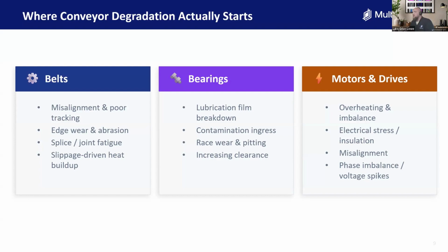And I think that there's something that's forgotten when we look at condition monitoring. It's for the operational zone - no, it's not. It's a lot of baseline data that can be used during that installation of quality, that commissioning, that understanding. And it was one thing that always used to blow my mind. You get a factory acceptance test, and there was not one standard in there about normal operating conditions. Not many OEMs even classified the vibration classification against ISO standard. So it was just weird.